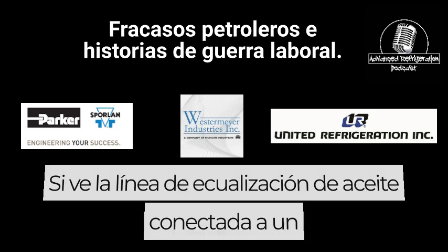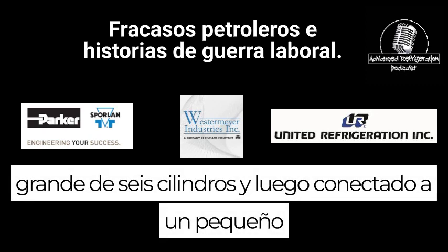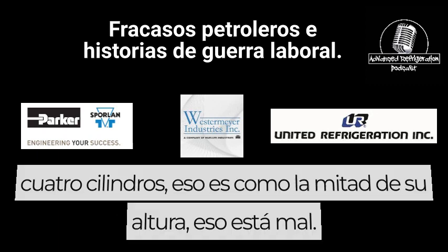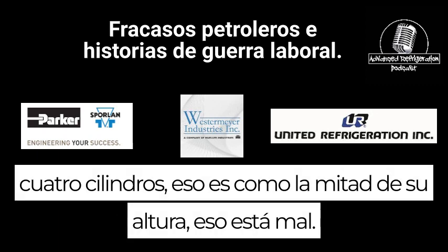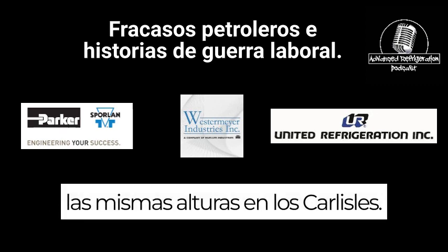If you see the oil equalization line hooked up to a big 6-cylinder and then hooked up to an itty bitty 4-cylinder that's like half its height, that's wrong. Someone screwed up. The compressors actually have to be the same heights in the Carlisles.